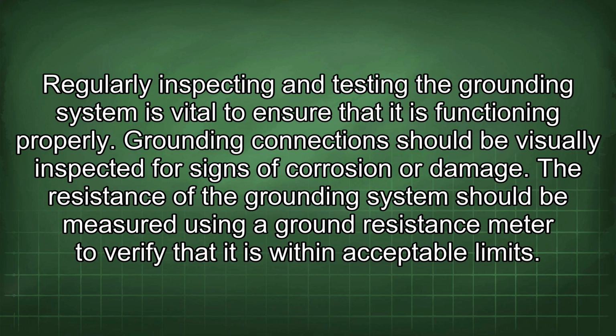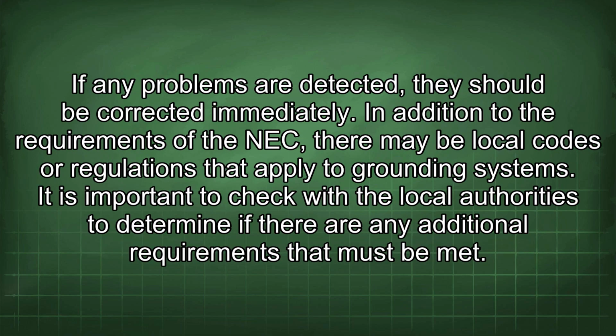Grounding connections should be visually inspected for signs of corrosion or damage. The resistance of the grounding system should be measured using a ground resistance meter to verify that it is within acceptable limits. If any problems are detected, they should be corrected immediately.